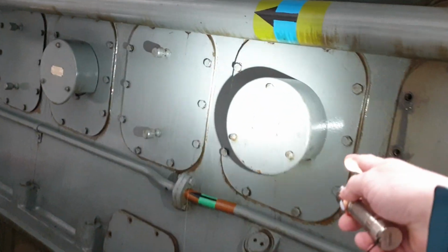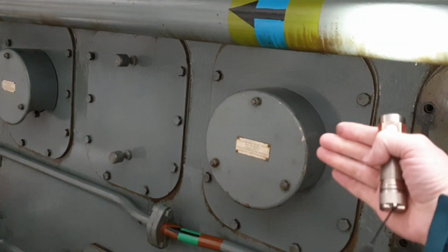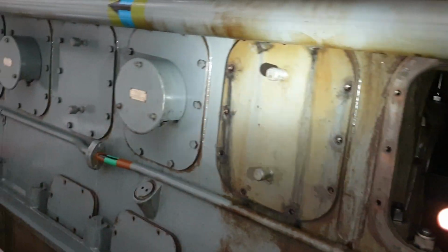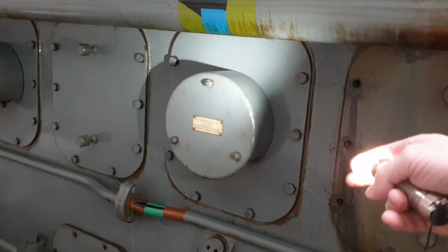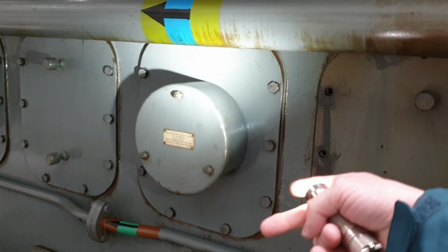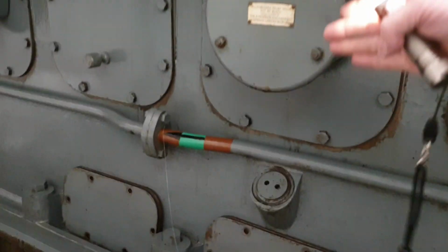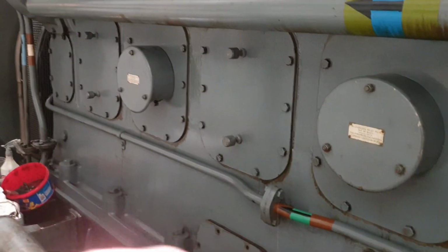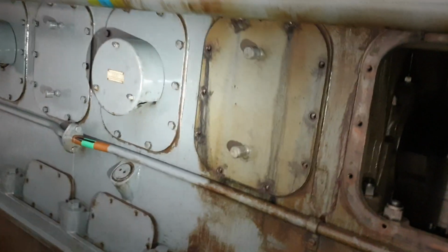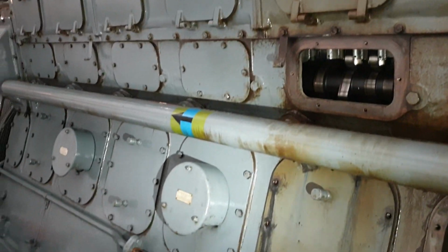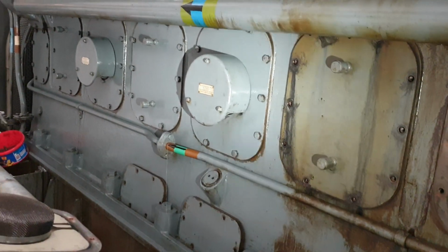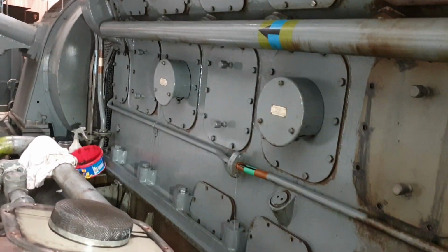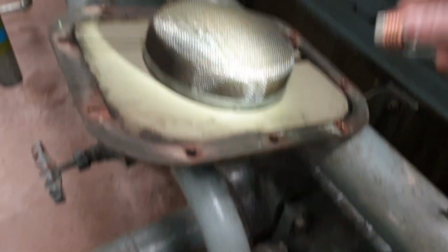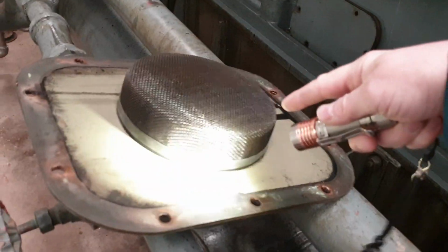These are the blast doors. There's basically a valve on the other side under pressure from a spring, and if there's any explosion in there, when the oil turns to a vapour and explodes due to the bearing getting so hot, it glows and ignites the mist. It will blow this out and the flames come out the bottom instead of blowing the panels off. In theory that's what happens, but apparently there's been quite a lot of incidents of these doors being blown off. Look, that's one of those on the other side of it.